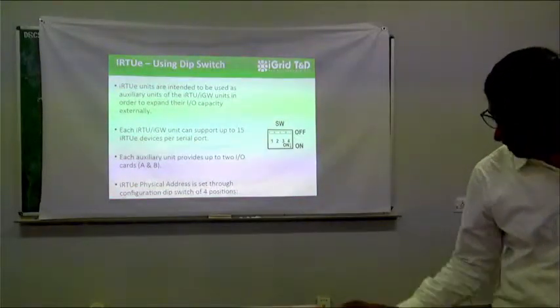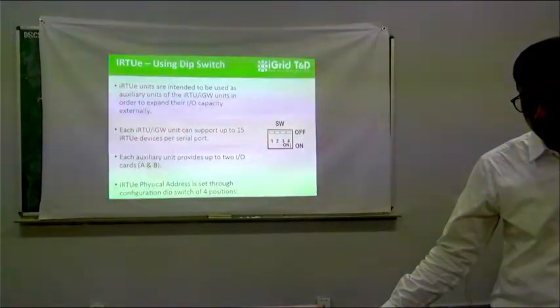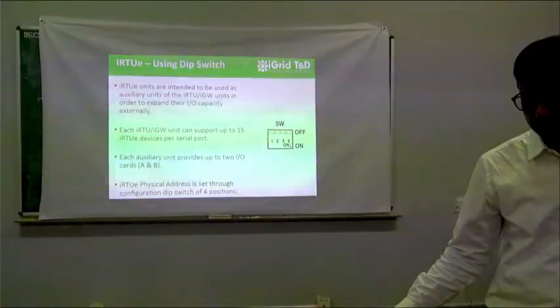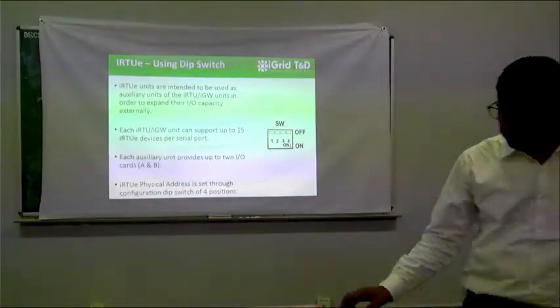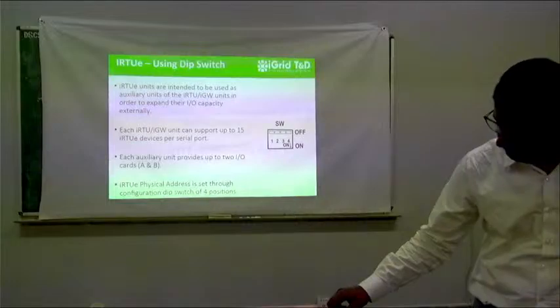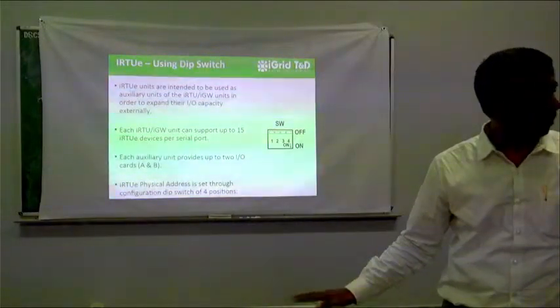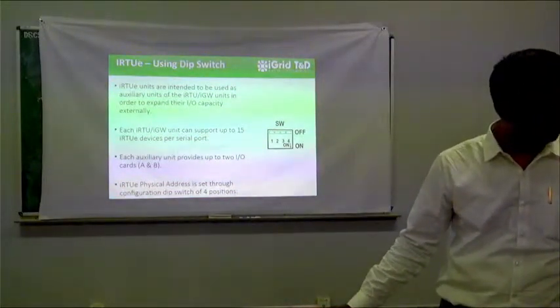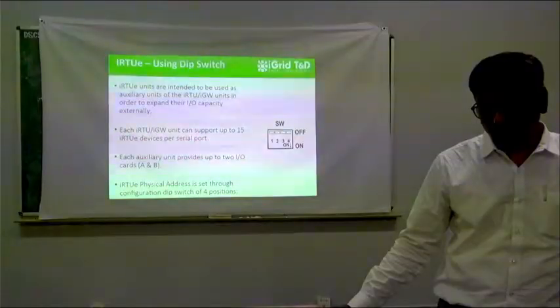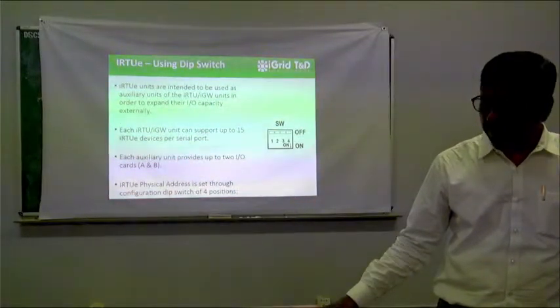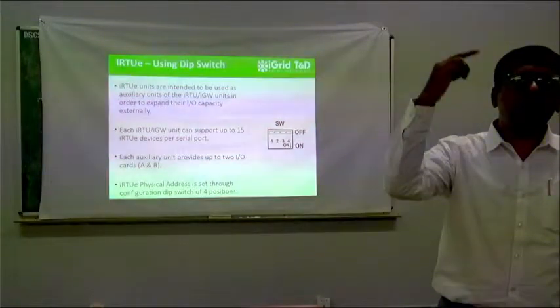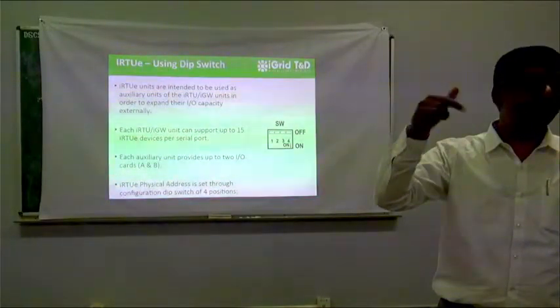Similarly, for my extension units, we have what is called a dip switch. Using that dip switch, I can set the ID of my extension unit. And from a single port of my main RTU, I can connect up to 15 devices.